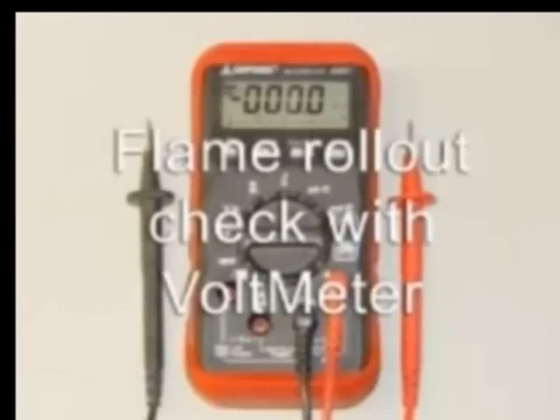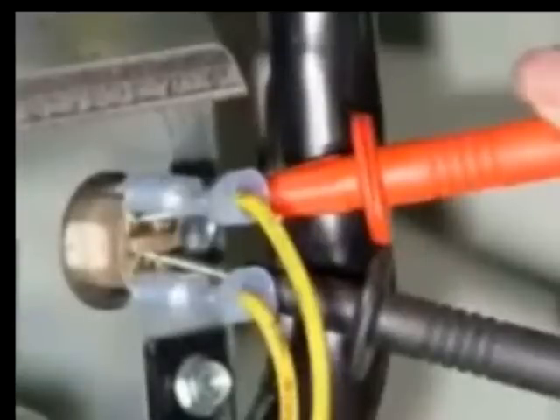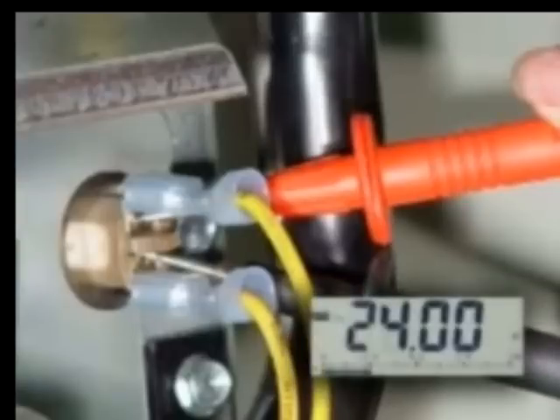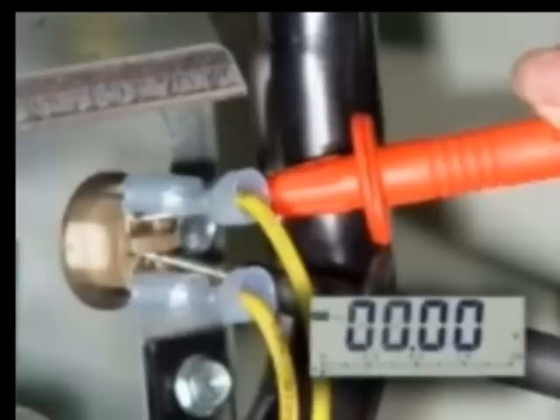Flame Rollout Check with Voltmeter - Call for Heat: Place your voltmeter leads across the limit switch terminals. You should measure zero volts if the limit is closed. If the limit is open, you will measure 24 volts.